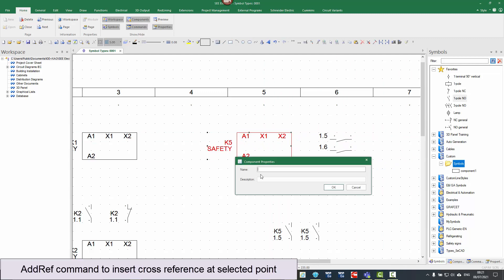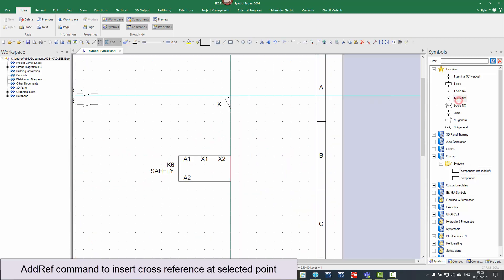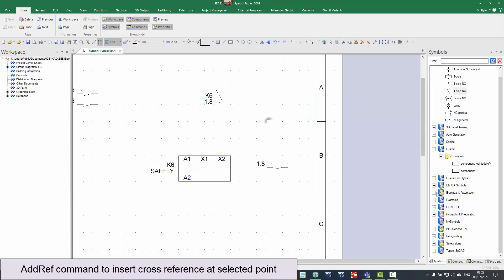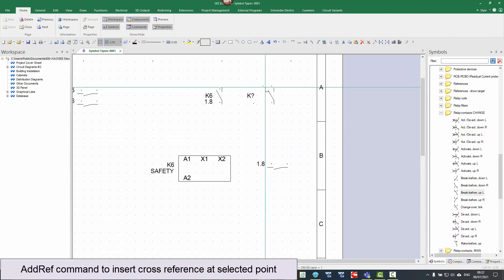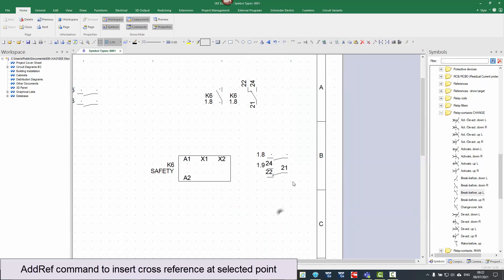If I drag and drop and save that to the symbol library, whenever I bring that symbol in and start using contacts, the cross reference appears in the specified position. We can also place in relay contacts — for example, a changeover contact — and that information appears in the cross-referencing display. So to summarize: we started with a component where there was no real cross-referencing. We can force it to have a cross-reference with another component, or say it's a component with auxiliary contacts, or a component with auxiliary contacts and the contact cross-reference symbol. And then we can use the add ref command to specify exactly where the cross-reference is going to appear.